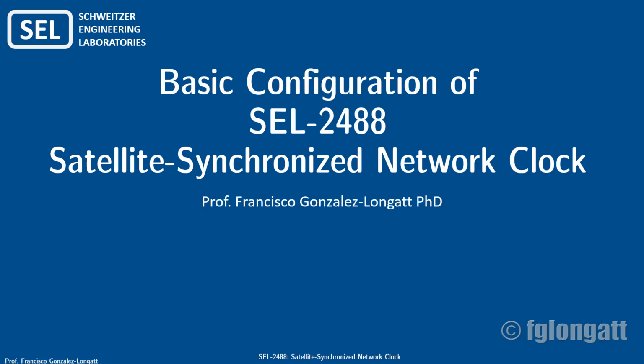Basically, what I have done is one of the steps that you need to do when you are commissioning this device at a station. We create an administrator account using the web server, and to do that you need to establish the communication between the laptop and the SEL device.